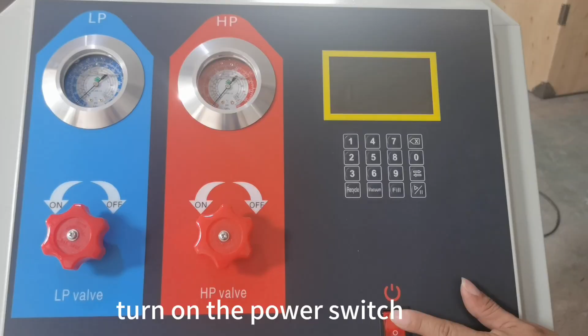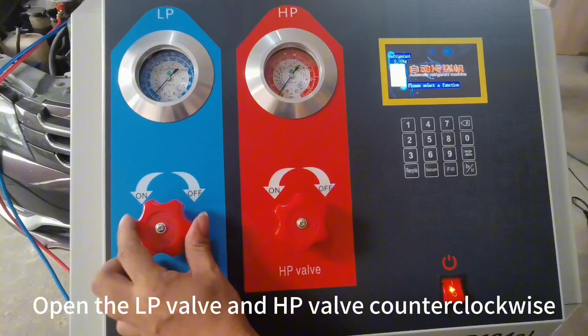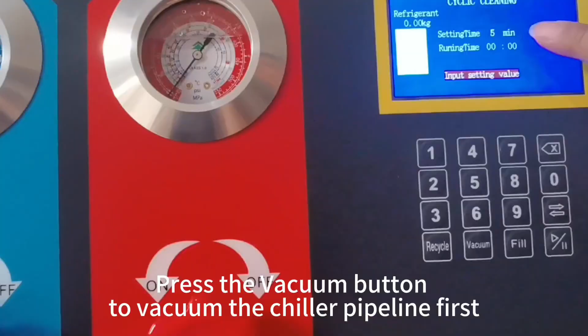Connect the power supply. Turn on the power switch. Open the LP valve and HP valve counterclockwise. Press the vacuum button to vacuum the chiller pipeline first. When the high and low pressure gauges are minus 0.1 MPa, it means vacuuming is complete. Turn clockwise to open the high and low pressure quick connector.